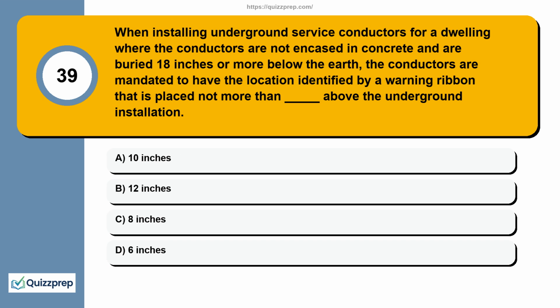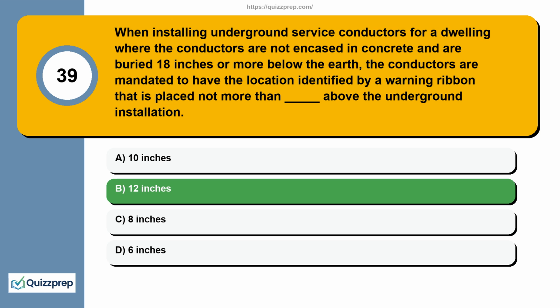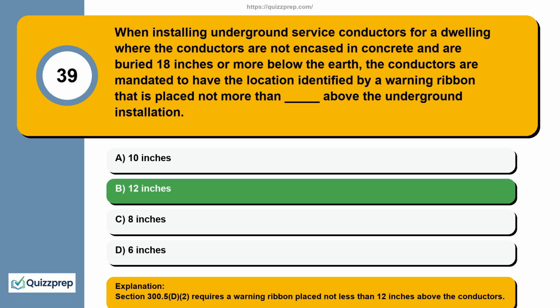Question 39. When installing underground service conductors for a dwelling where the conductors are not encased in concrete and are buried 18 inches or more below the earth, the conductors are mandated to have the location identified by a warning ribbon that is placed not more than what distance above the underground installation? 10 inches, 12 inches, 8 inches, 6 inches. Section 300.5(D)(2) requires a warning ribbon placed not less than 12 inches above the conductors.